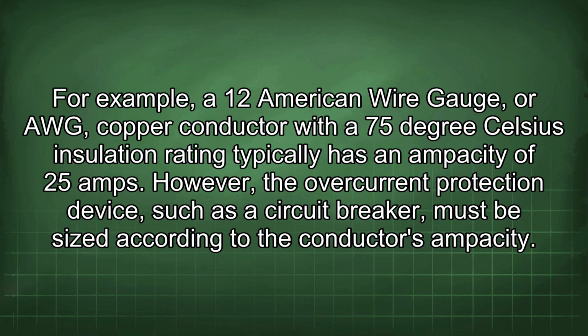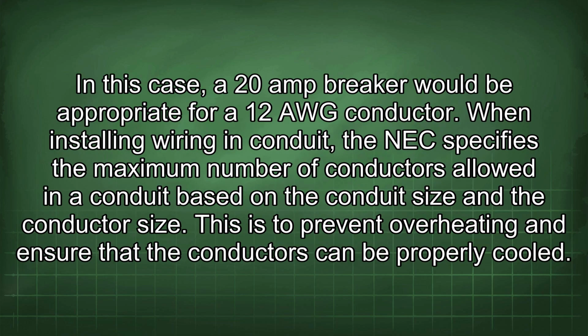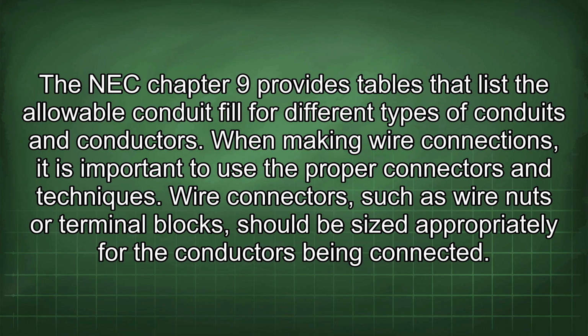However, the overcurrent protection device, such as a circuit breaker, must be sized according to the conductor's ampacity. In this case, a 20 amp breaker would be appropriate for a 12 AWG conductor. When installing wiring in conduit, the NEC specifies the maximum number of conductors allowed in a conduit based on the conduit size and the conductor size. This is to prevent overheating and ensure that the conductors can be properly cooled. The NEC Chapter 9 provides tables that list the allowable conduit fill for different types of conduits and conductors.